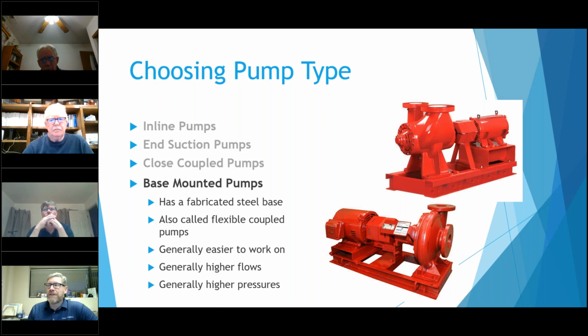So you do want to make sure if you have a VFD driven pump that you're using the right coupler on them. Most of the ones that we use are either like a Woods Duraflex, which is the typical black spider looking thing. It's an EPDM coupler, or the Sureflex, and it's got the little bubble on it. Both those are acceptable for VFD duty. I've seen plenty of those where they're used in the orange sleeve and it just chews them up, and the spine, the little spider thing sticking out, they get really pointy and everything like that. So you just want to make sure you get the right one. These here, since they're mounted on a base and they're mounted on the floor, you can pretty easily get 250 pound working pressure. Some of the larger ones you can get up to like 400 pounds. So they're made for high-rise type buildings, or applications where you got much larger pressures.